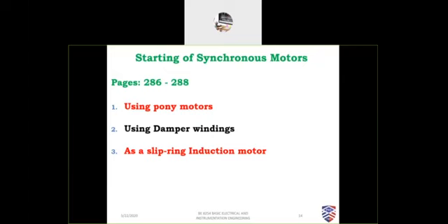Now you can have a question. Why should we do this, sir? Already we have a motor, the induction motor, let it run. But the induction motor is not running at the synchronous speed, number one. Number two, in all motors, when the load is given, the speed goes down. Whereas in the synchronous motor, the speed does not go down; it constantly maintains the speed with the frequency. That is very, very important. Got it? Other motors, when loaded, the speed will go down. Whereas here, instantly it goes down, but finally it matches the speed.